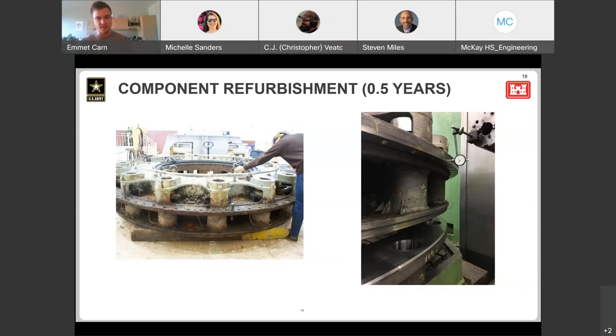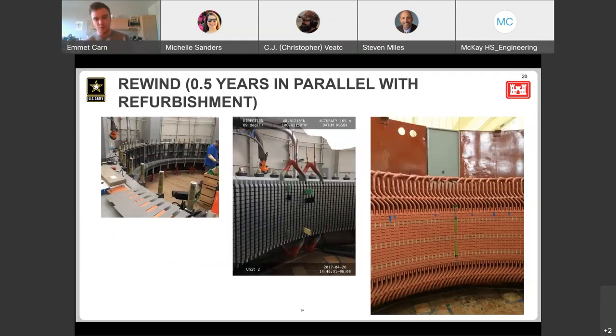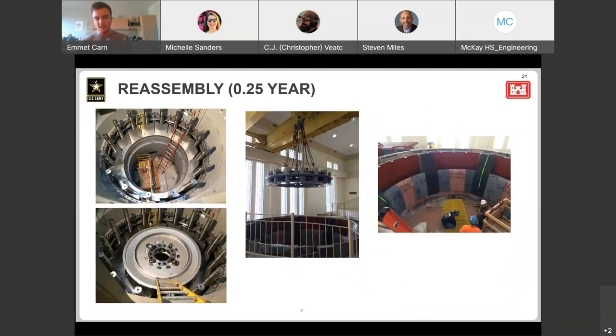So we'll do a lot of inspections and cleaning of those components. We'll also do what's called a rewind of the generator. I don't work on this too much since I'm a mechanical engineer, but it's essentially a refurbishment of the generator, and that can take about half a year, done in parallel with all the turbomachinery work. Once everything is refurbished or replaced and ready to go, that's when we reassemble the unit back to where it was, in the reverse order of disassembly, which can take about a quarter of a year as well.